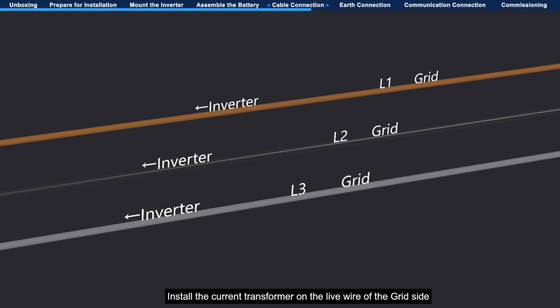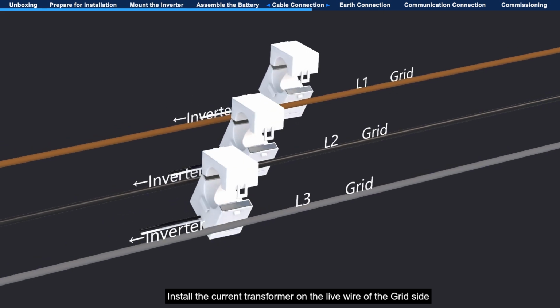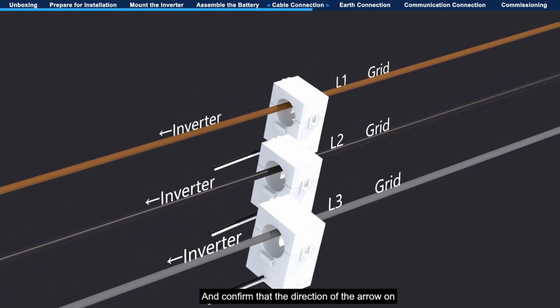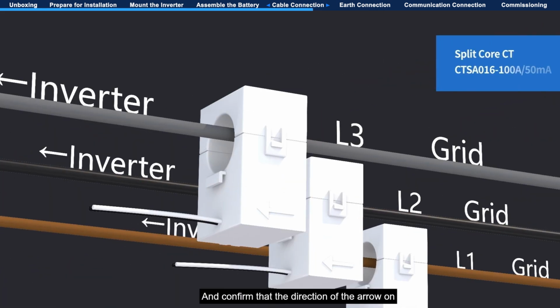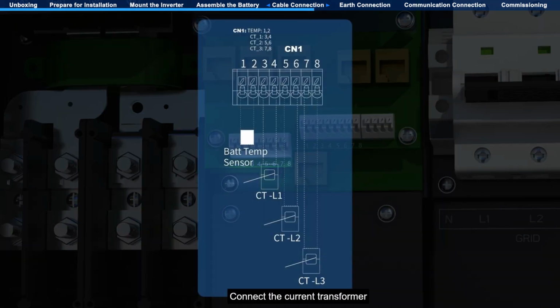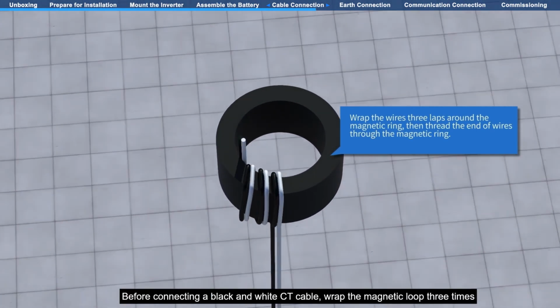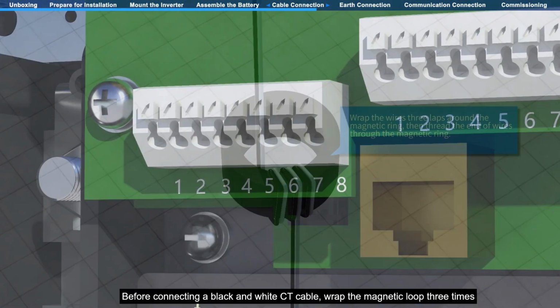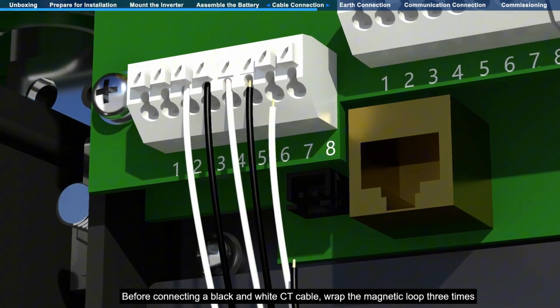Zero export connection. Install the current transformer on the live wire of the grid side and confirm that the direction of the arrow on the current transformer points towards the inverter. Connect the current transformer according to the prompts in the manual. Before connecting a black and white CT cable, wrap the magnetic loop 3 times.